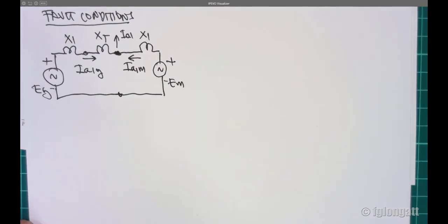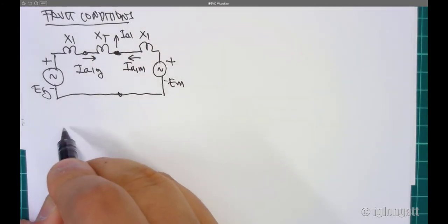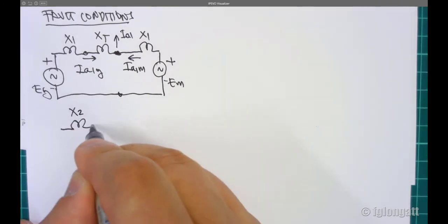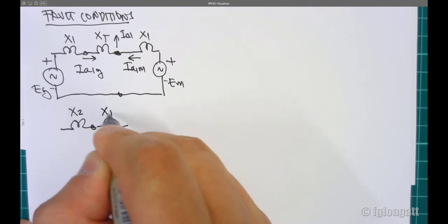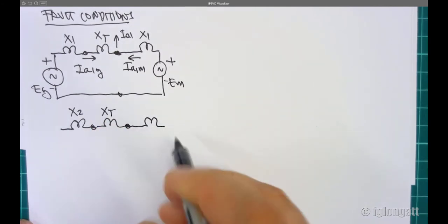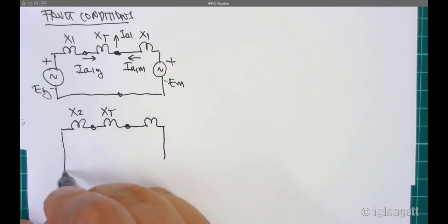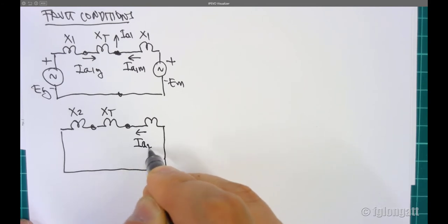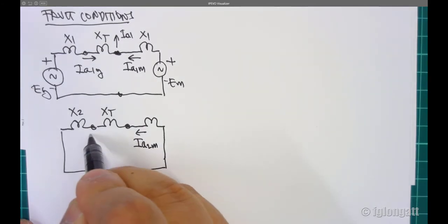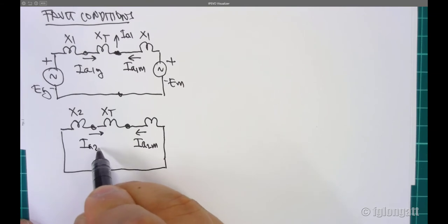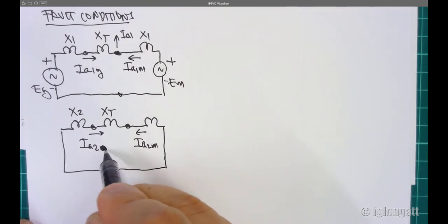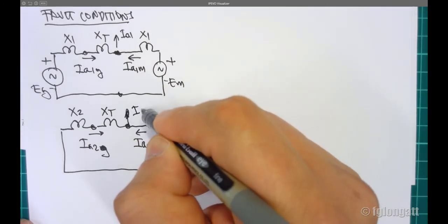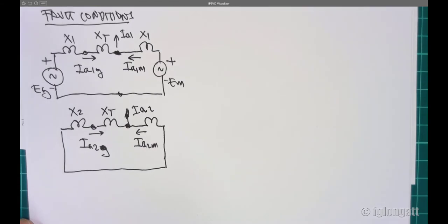Okay? What's about the negative sequence? In the negative sequence, we have here the negative sequence. We have the transformer here. And now what we have here is, this is the negative sequence contribution coming from the motor. This is the negative sequence contribution coming from the generator. Sorry, this is the generator. When they zoom over here, this is the negative sequence current, okay?